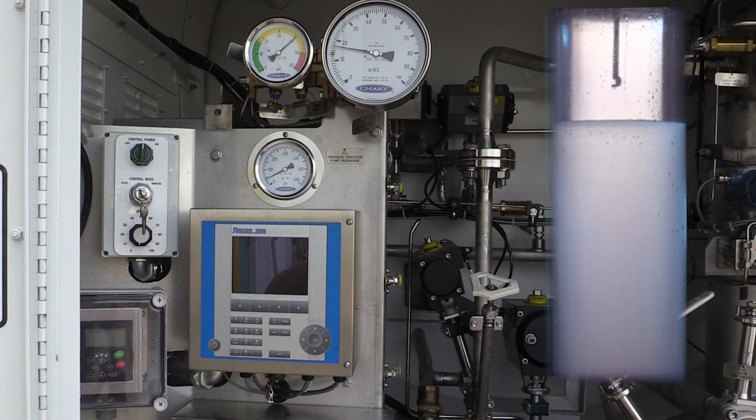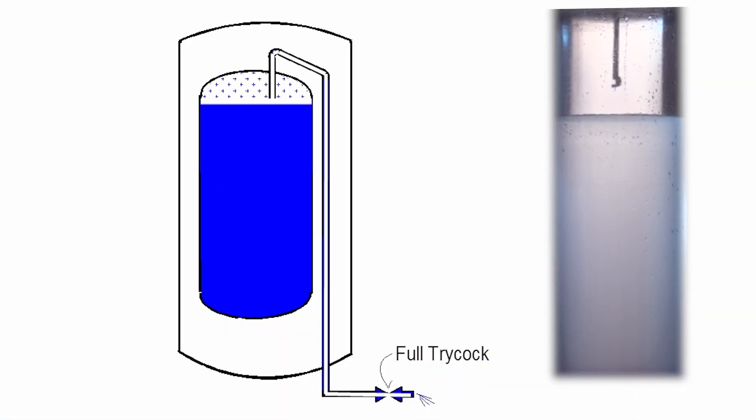There are temperature and density changes that occur in the product that must be accounted for. The fluid inside the tank slowly warms over time and the liquid level expands. This extra vapor space is called the ullage space. The tank has a trycock overflow valve. This valve will inform the driver filling the tank if the liquid level is exceeding the safe fill level.